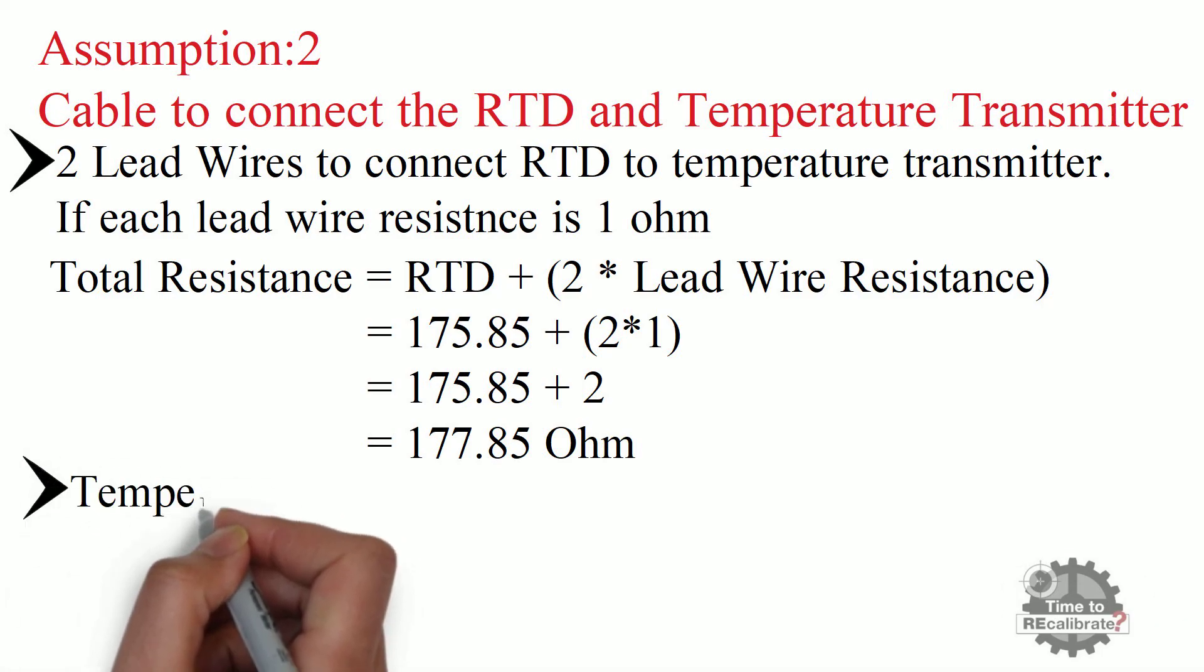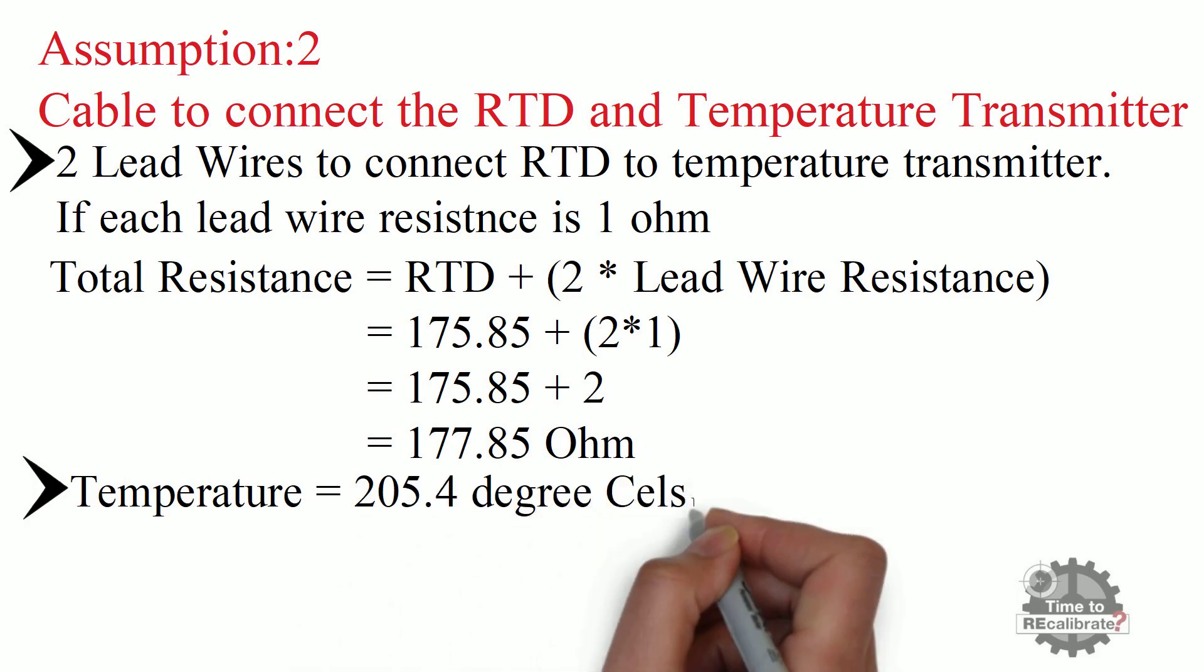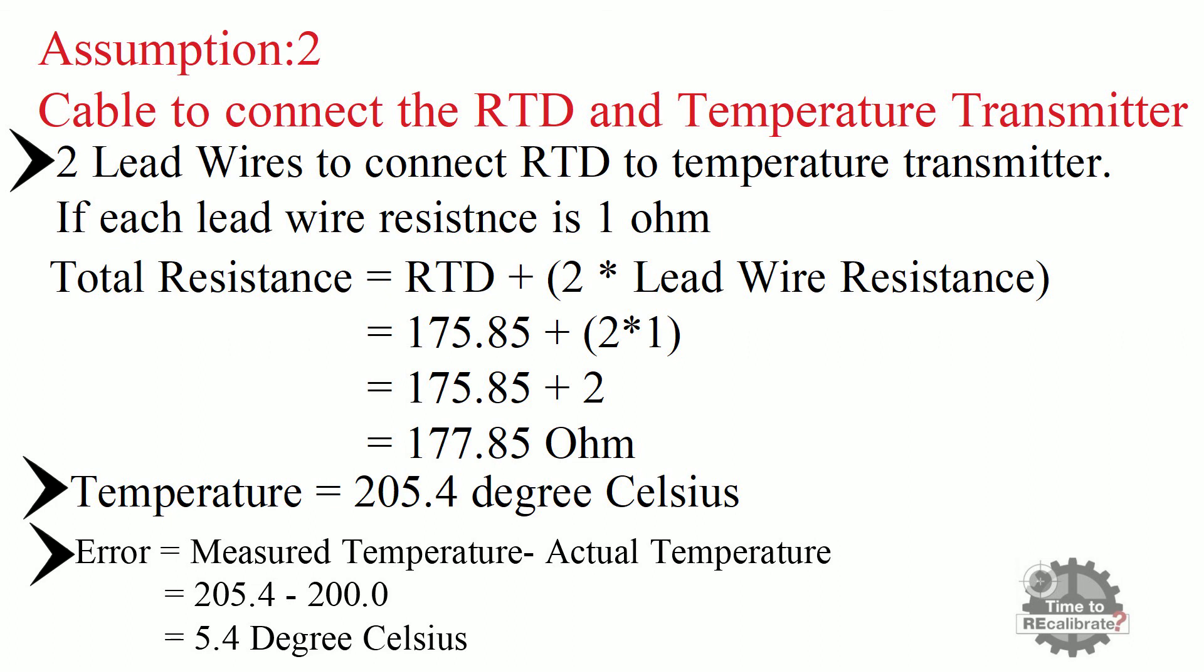In this example, the temperature according to the total resistance value is 205.4 degrees centigrade, which is incorrect temperature. And if we calculate error, we will get 5.4 degrees Celsius error. In other words, the lead resistance introduced measurement error of 5.4 degrees centigrade.